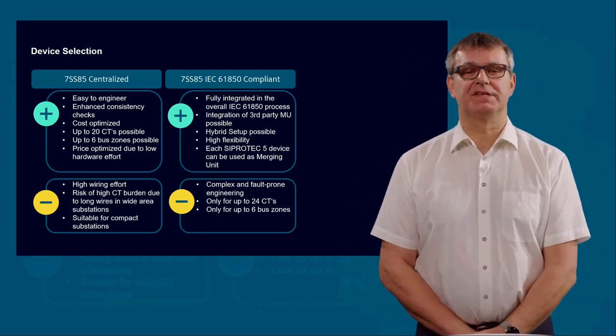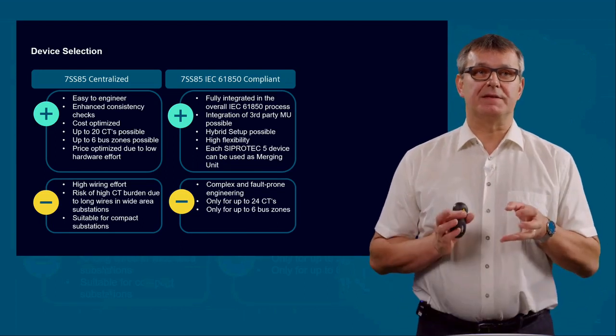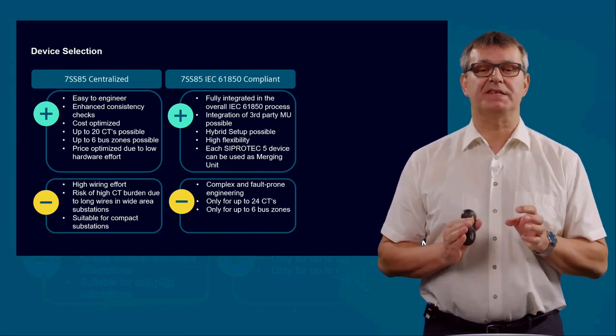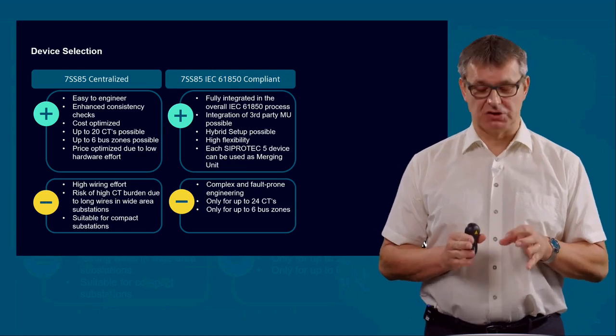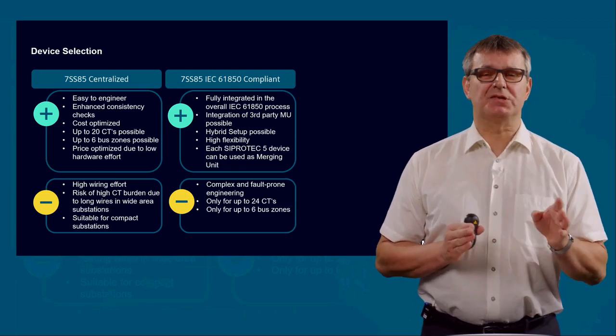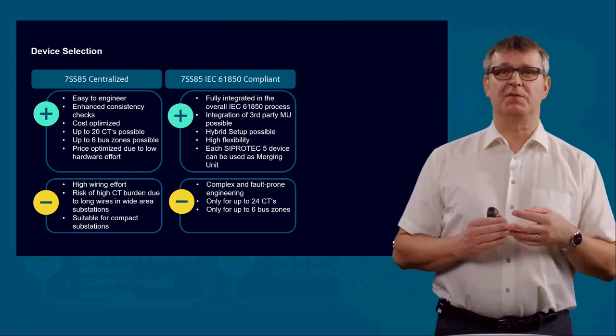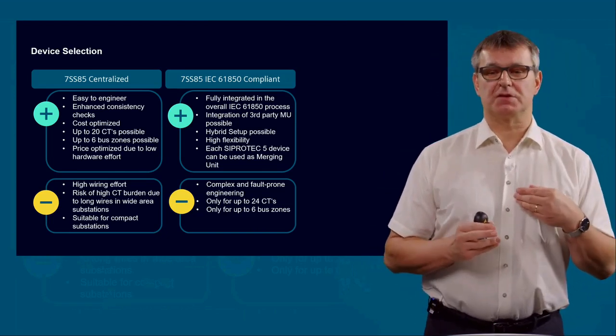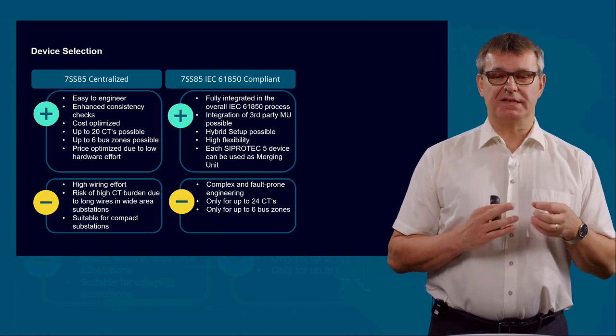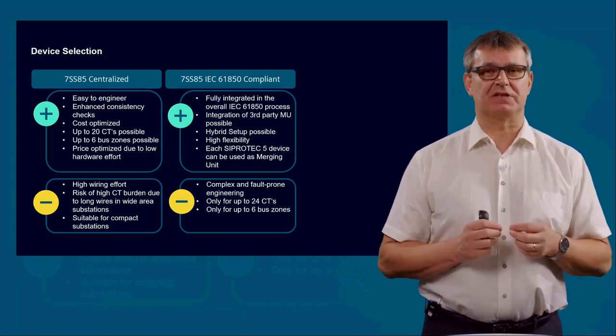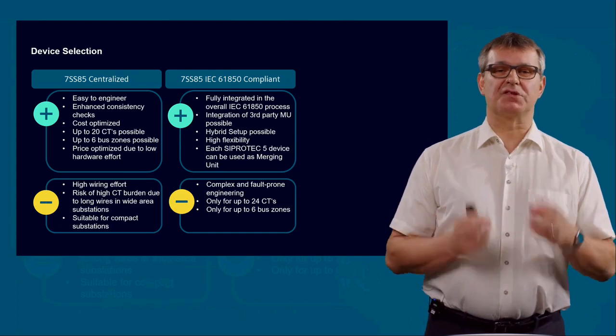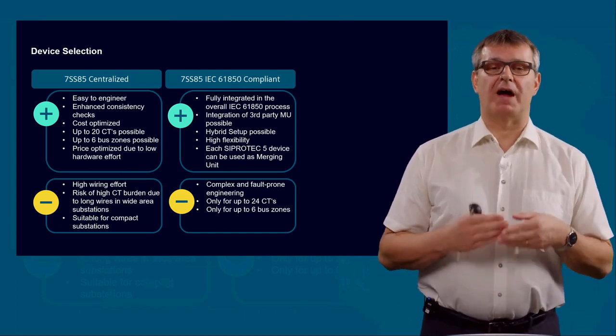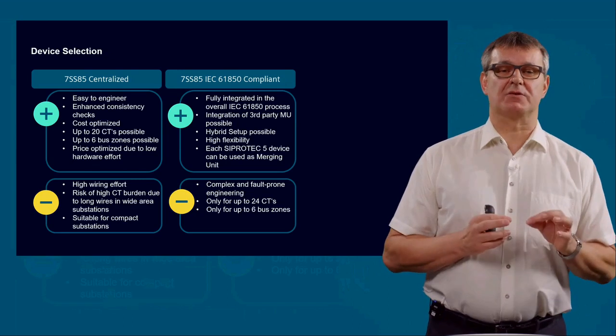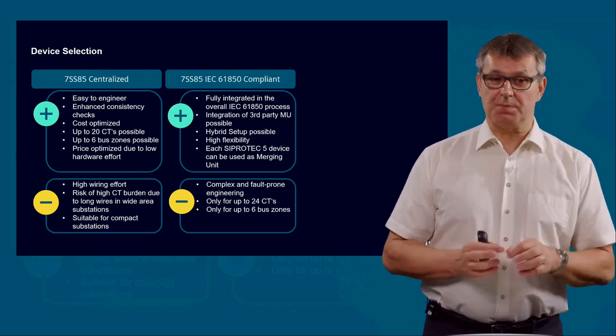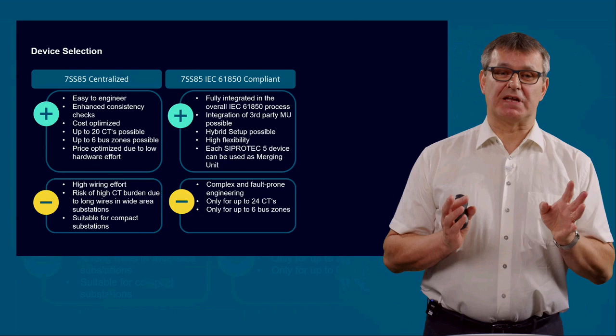A little bit the disadvantages. It may be quite complex and fault-prone engineering. Maybe not so much the assignment of the current information to the device, but doing all the disconnector positions of the several disconnectors, the positions of the circuit breakers, the trip commands, and wiring this via GOOSE engineering. It's not so easy a job. It can be done, it's not complicated, but the engineer has to be very concentrated.